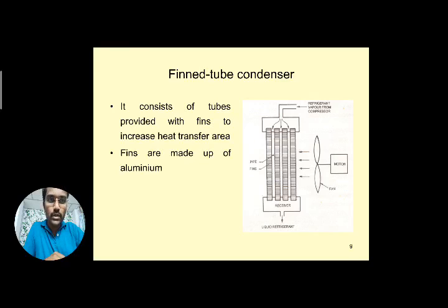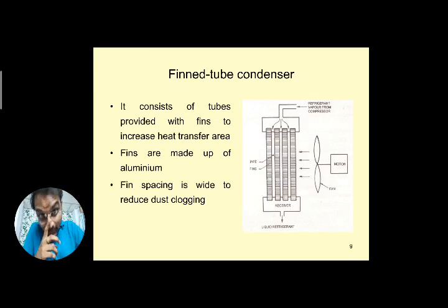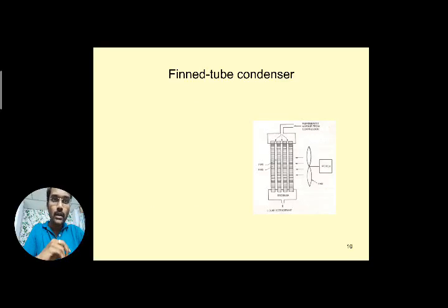The fins are mostly made of aluminum, and the spacing is wide to reduce dust clogging. That is also one thing. If you provide a very narrow gap between two fins, dust clogging is the main problem. So a wide gap is provided between each fin, which reduces dust clogging, and effective heat transfer takes place. This is regarding the finned tube, where, if you observe, there are also plate surfaces.